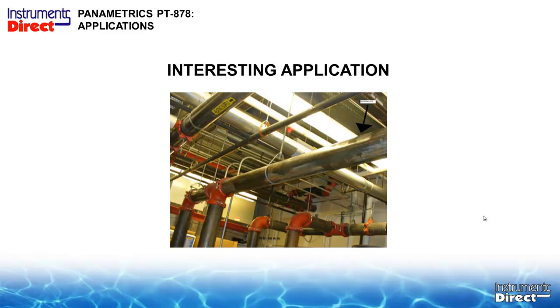An interesting application: if you go to a big box store and look up, you'll see gorgeous plumbing across the ceiling with these pretty connectors on there with their quick attach, and they basically clean up the whole hydraulic situation. And they do a very good job hydraulically, except at the installation point of these devices, some of them using a thinner pipe wall material, which requires that the end of the pipe be ferruled, for a bad description, like an ice cream cone, to adapt to these fittings. That will cause you additional disruption.